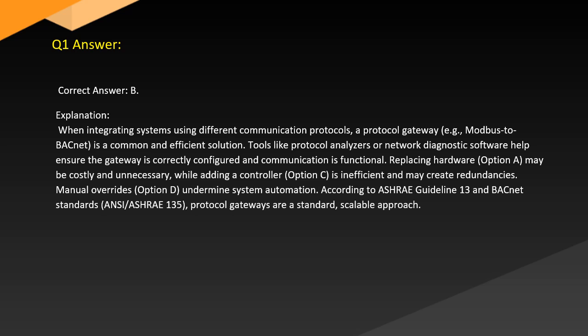Replacing hardware, option A, may be costly and unnecessary, while adding a controller, option C, is inefficient and creates redundancies. Manual overrides, option D, undermine system automation. According to ASHRAE Guideline 13 and BACnet standards in ASHRAE 135, protocol gateways are a standard, scalable approach.